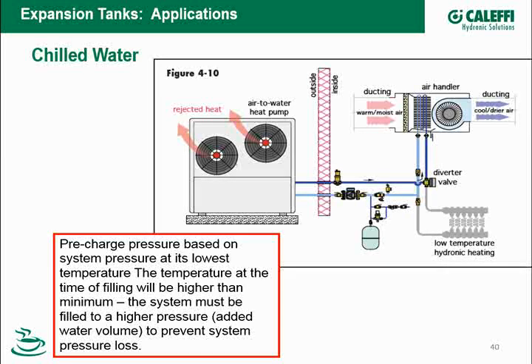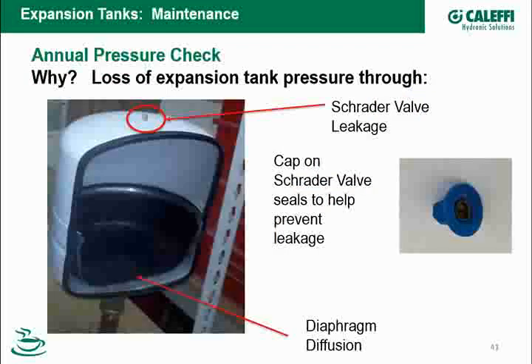Now, the final part of this is maintenance. Expansion tank manufacturers recommend that the pressure is checked on an annual basis. Why? The tanks can lose pressure. The first place is the Schrader valve on the top of the tank, used for setting the pre-charge and making adjustments. Tanks come with a cap for the Schrader valve. Use the cap. The cap is actually the seal. If I don't have a cap on there, the tank will lose air as it leaks by that Schrader valve. It's not the most airtight seal that you'll see out there.